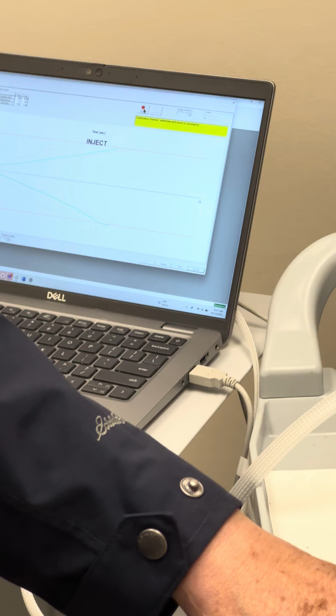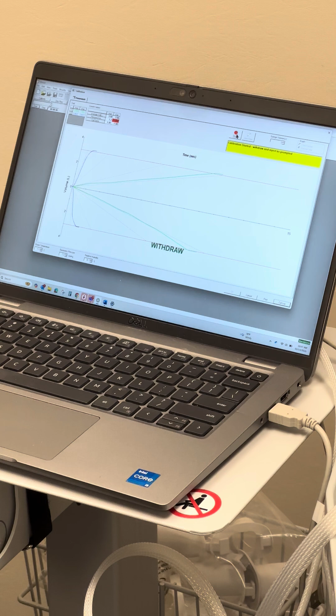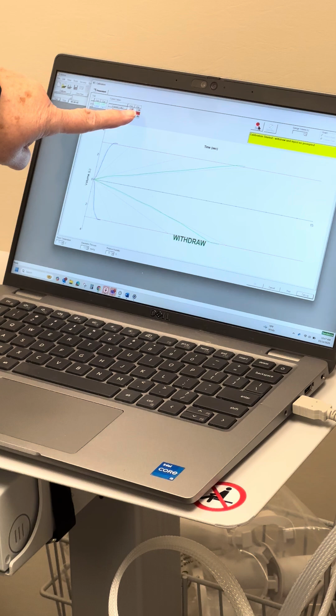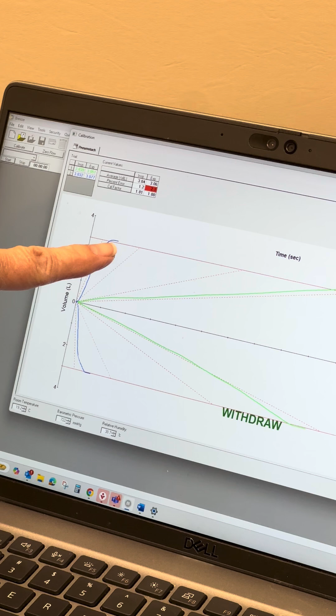So the next one I'm actually going to do, I'm going to do the fast one. And when this is a new calibration, it does take a bit of time to get the feel of those different flow rates. And now you'll see that I have a red box up here, and if you look closely you can see that my flow line is just slightly above my 3-liter volume, so it's probably not going to pass calibration, so I'm just going to stop.